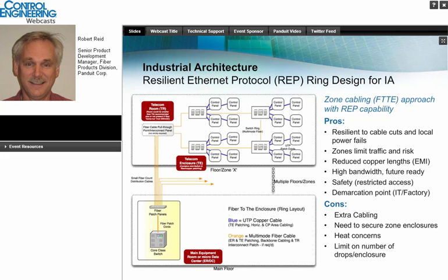So what I can do is, with the mini switches that are in these TEs, or if it's a pizza box switch, I can take the uplink from one side and put it into the next switch and basically form these switches in a ring. And the beauty of that is if I have a power outage on one of these little zones of automation, if the power to the TE goes down, I still have comms everywhere else. I still have communication between the remaining TEs. This is resilient. This is network resilient.